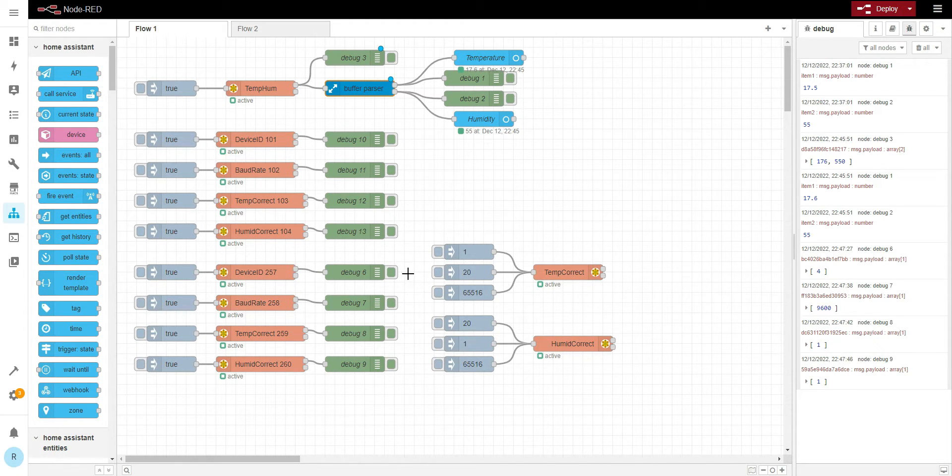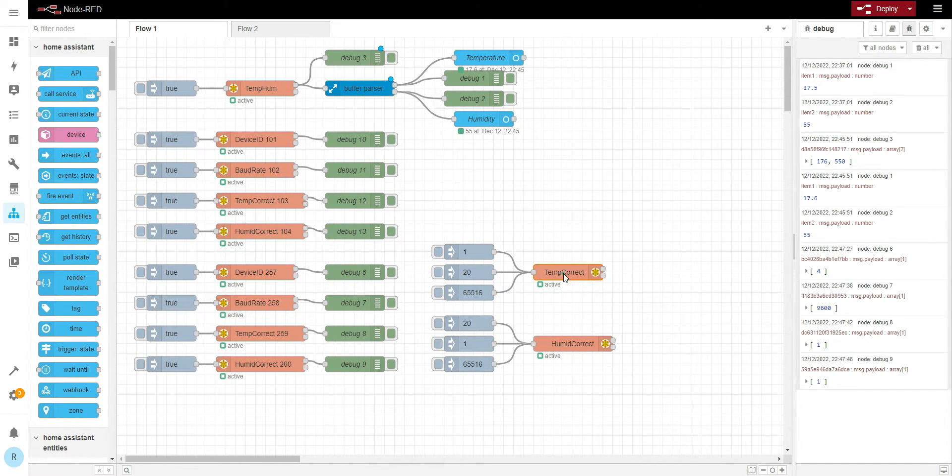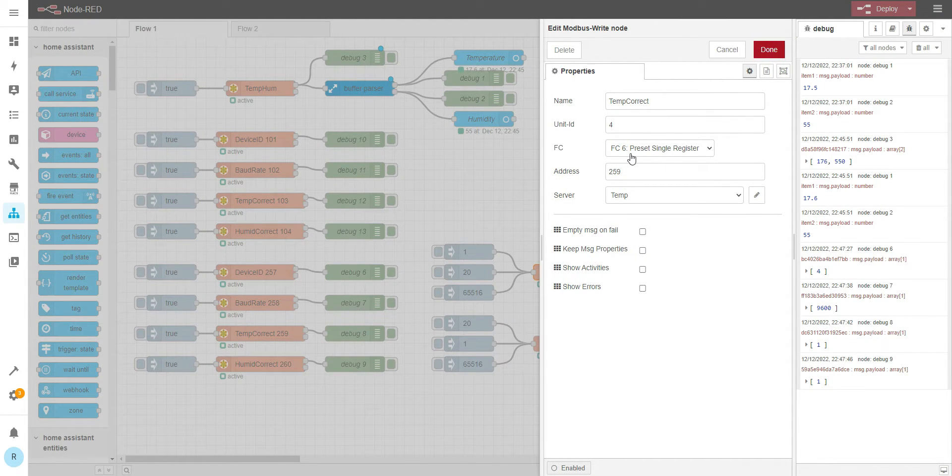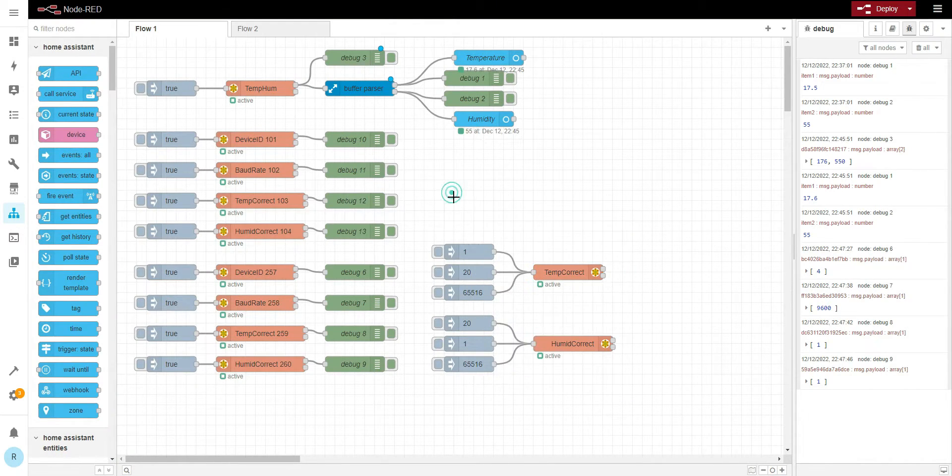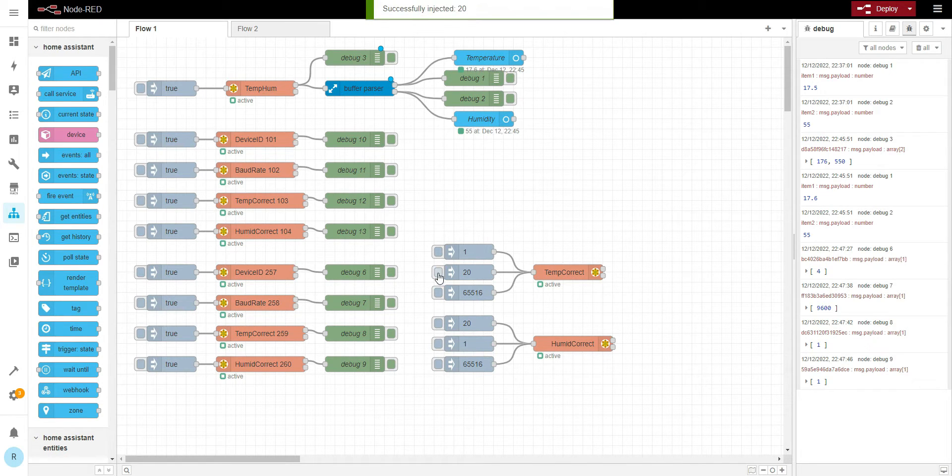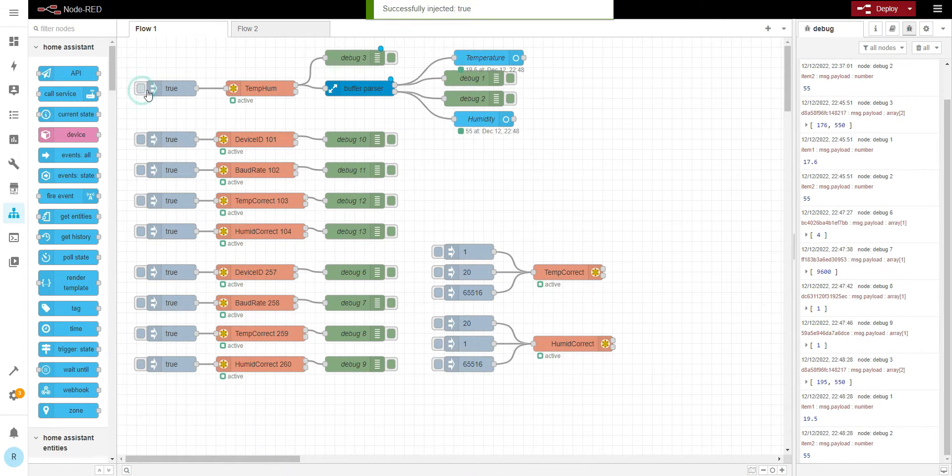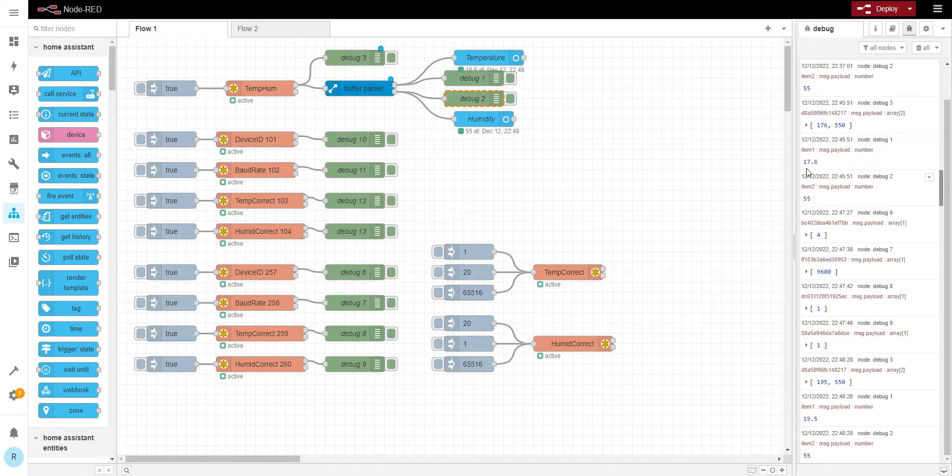How are we going to change the temperature correction? Basically, we're going to be using function code 6, preset a single register. So let's redo this, read the temperature. And we got 19.5 instead of 17.